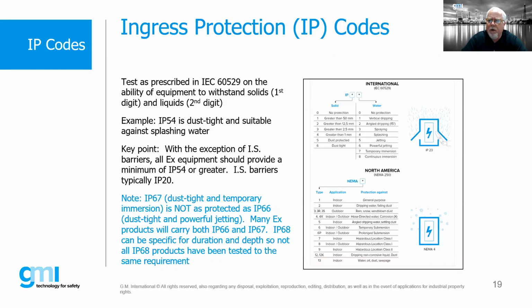But NEMA 4, NEMA 4X is commonly what you might see with a lot of hazardous location equipment here in the United States. 4X is basically a corrosion resistant version, very similar to NEMA 4. NEMA 4 is basically hose directed water, very similar to IP66. But again, there is not a direct correlation between IP codes and NEMA codes.